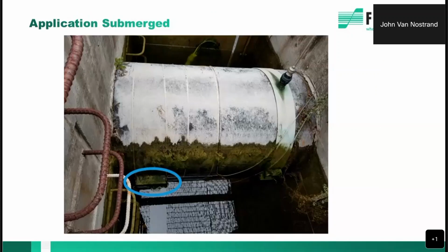This is a pump station at a major utility that could not turn this flow off. It's a 36-inch carbon steel pipe, and there's 20 million gallons a day of raw sewage that flows through the station. They'd like to know the number of gallons, but they could not turn it off. To install a Magmeter would be a massive undertaking here.